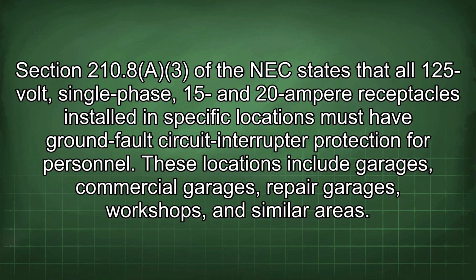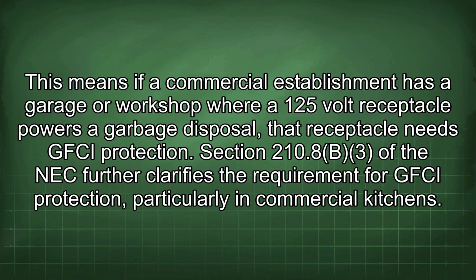These locations include garages, commercial garages, repair garages, workshops, and similar areas. This means if a commercial establishment has a garage or workshop where a 125-volt receptacle powers a garbage disposal, the receptacle needs GFCI protection. Section 210.8(B)(3) of the NEC further clarifies the requirement for GFCI protection, particularly in commercial kitchens.